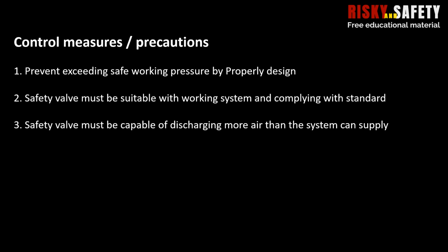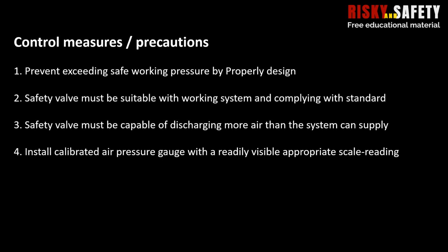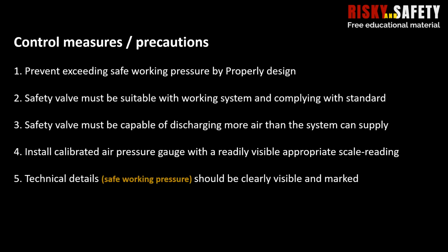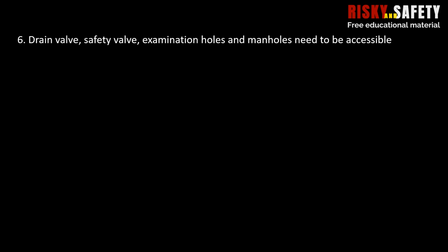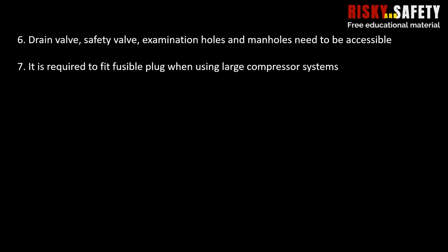The safety valve must be suitable for the working system and comply with standards, capable of discharging more air than the system can supply. Install an accurately calibrated air pressure gauge with a readily visible, appropriate scale reading. Technical details should be clearly visible and marked on the vessel. The drain valve, safety valve, examination holes and manholes need to be accessible. It is required to fit a fusible plug when using large compressor systems.